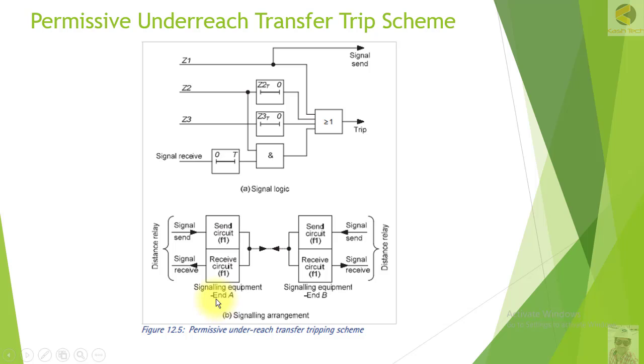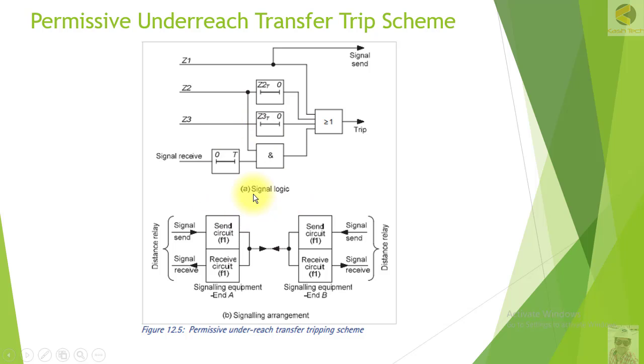At the remote end relay, as soon as it receives the signal and it has picked up in Zone 2 in the forward direction, if it is also picked up in Zone 2 in the forward direction, then it will trip with the given time T as per the setting. This is an example of the transfer trip scheme.